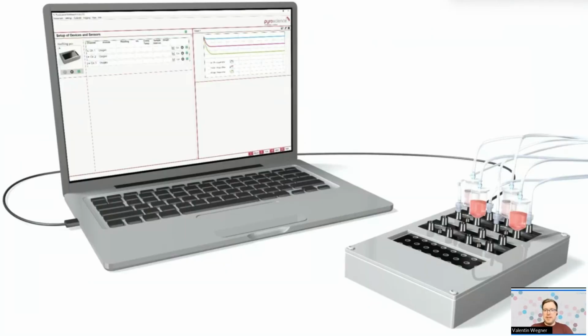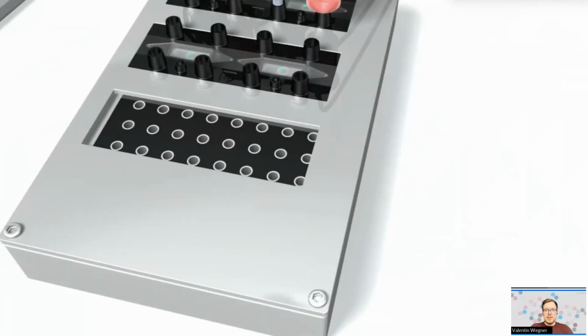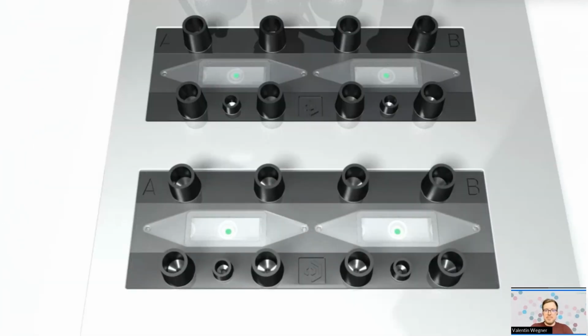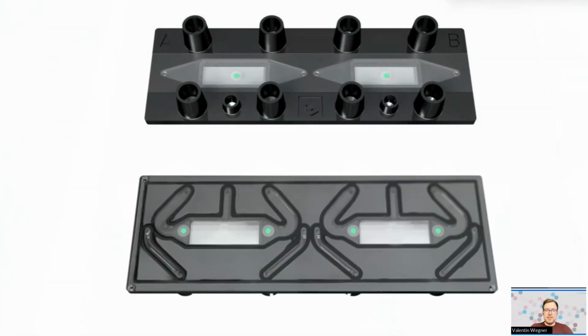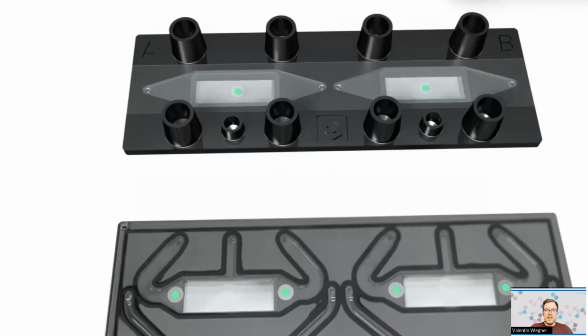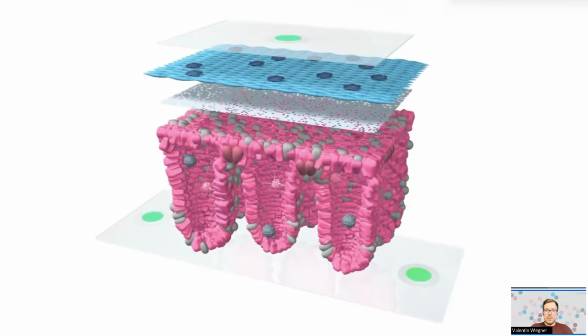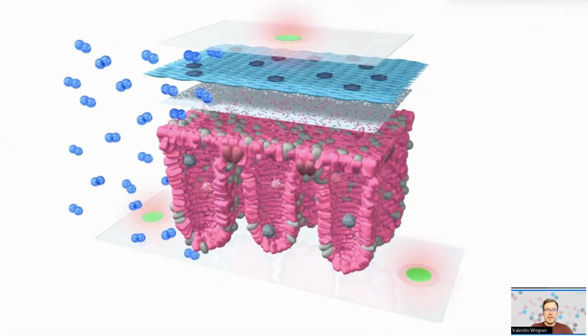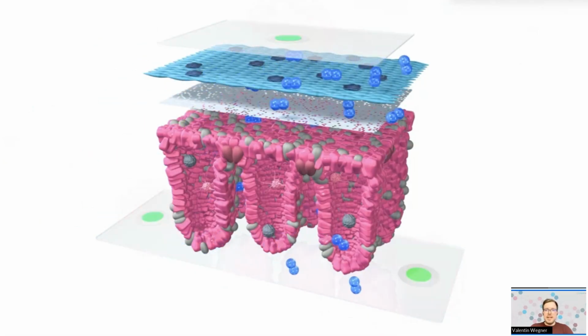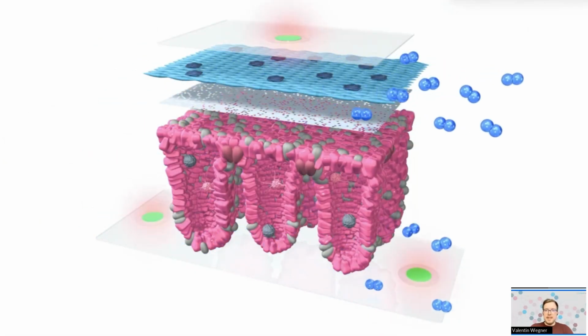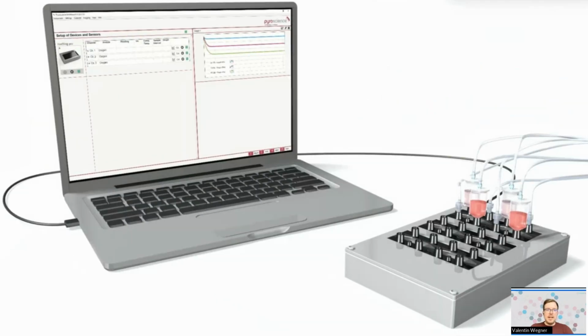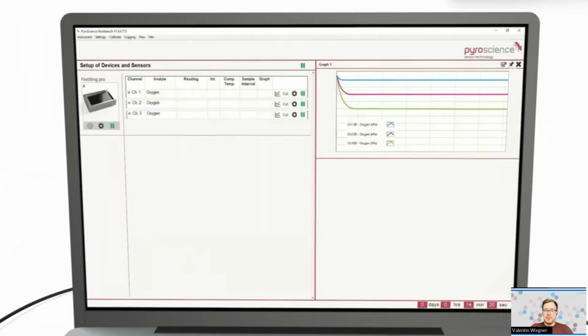It sits quite straight in there, so no problems with the measurement at all. And if we look now at how this all works on the fireplate, here again on our chip, you see one sensor spot in the top and two in the bottom channel. If we zoom in to the intestinal model, we see when oxygen enters, it is consumed within the model, and especially in the lower channel, we can measure how much is consumed, and we can live monitor that with the PyroScience software Stephanie already introduced.